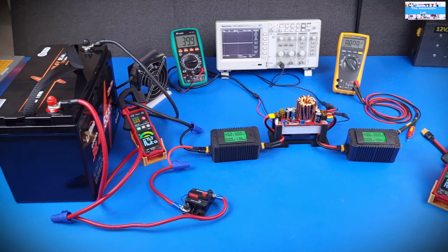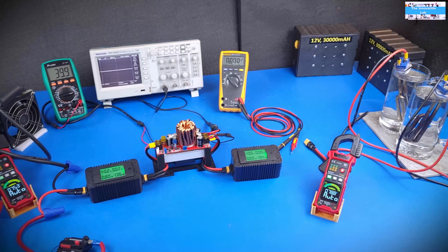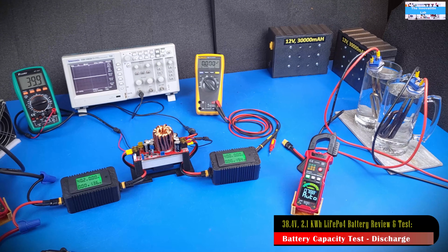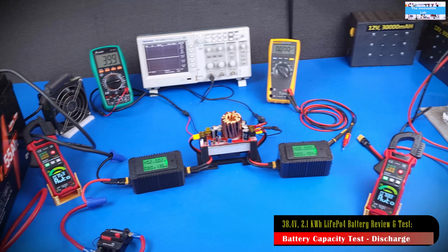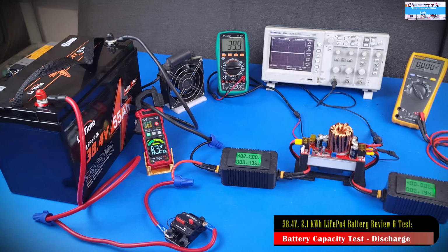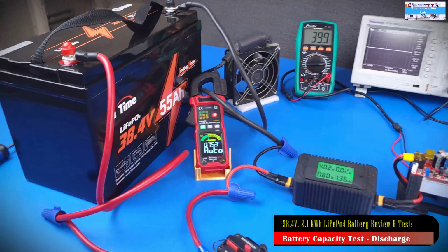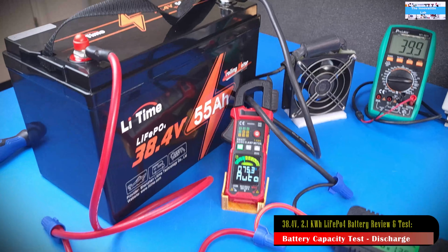The goal of the discharge test is to fully discharge the battery, and in the end we're going to look at the amount of energy delivered to our load, using that to verify or validate the manufacturer's battery capacity rating in watt hours.